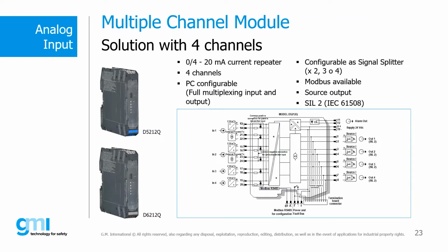The unit is PC configurable, can be used as a full multiplexing input and output. So we can have software that does not generate, but configures the input or the output equal to the sum, the addition. It's a small controller in this case. So it can also be used as a splitter or duplicator by 2, 3, or 4 times the input. So the same input I can send to 4 different outputs to the system. This unit is also available with the Modbus interface. It can also be a source output and is also certified for SIL 2 applications.